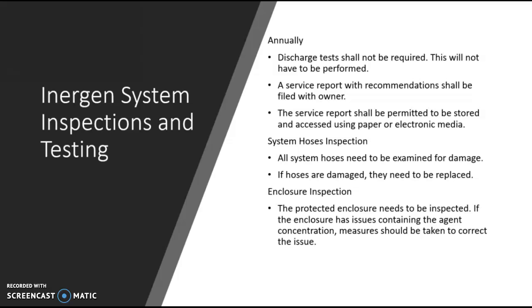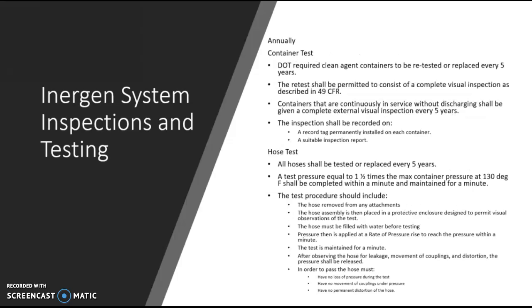Annual tests. Discharge tests are not required. It will not have to be performed. A service report with recommendations shall be filed with the owner. Service report shall be permitted to be stored and accessed using paper or electronic media. System hose inspections need to be provided, and enclosure inspections. And we'll get involved with the system hose inspection in just a minute. The container test is DOT required.